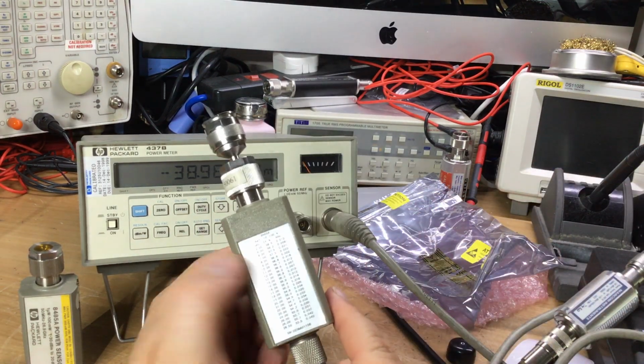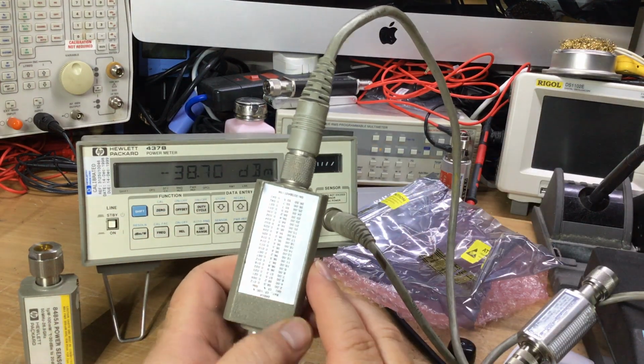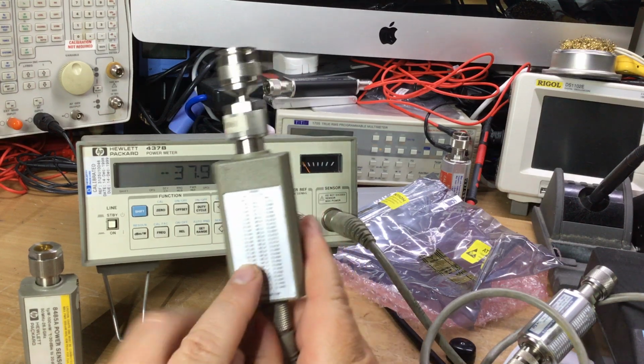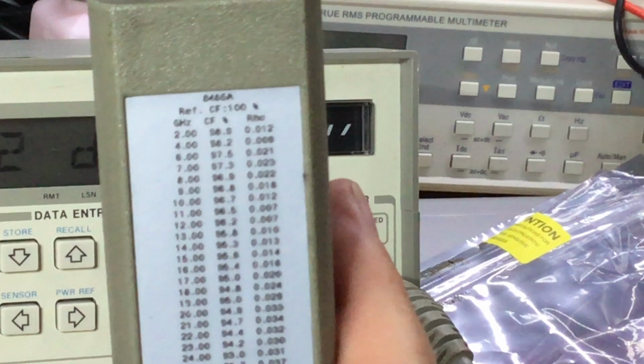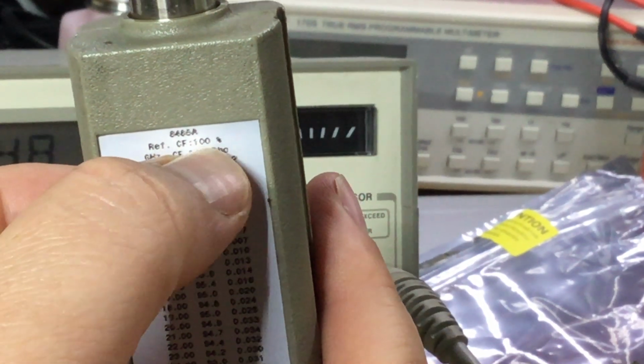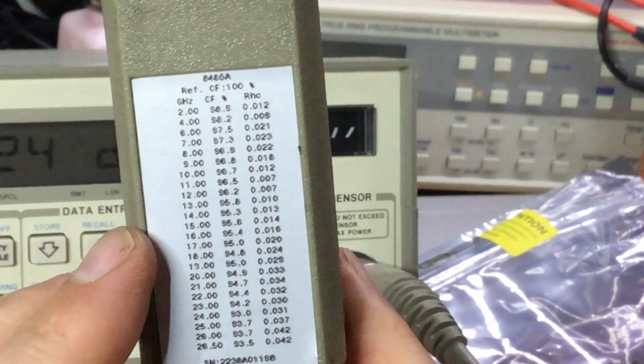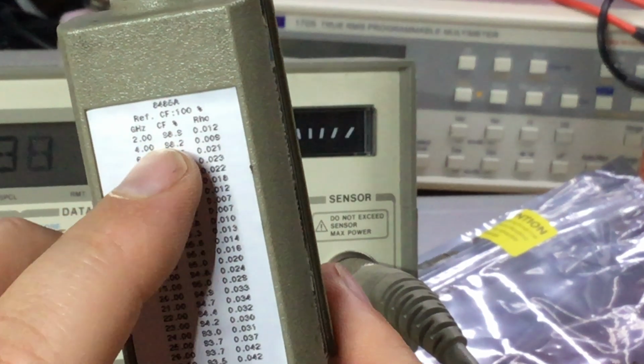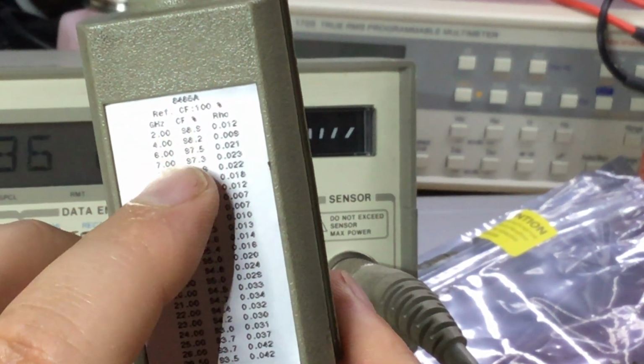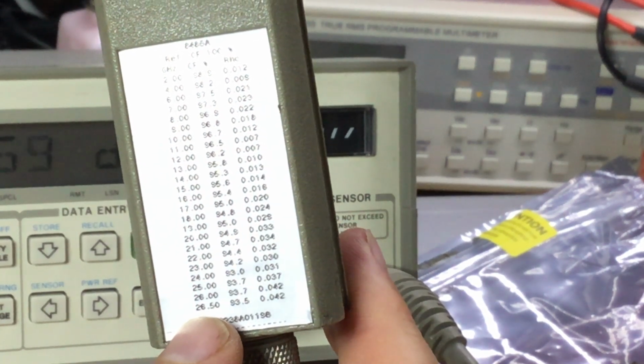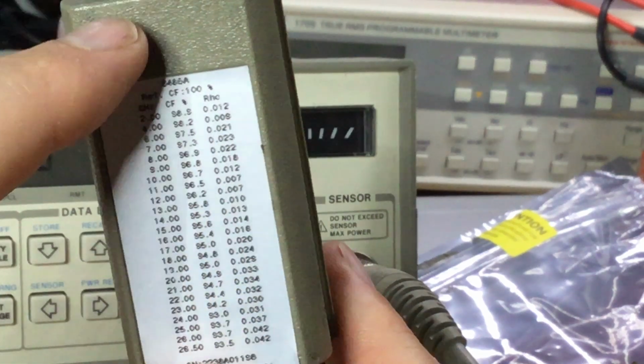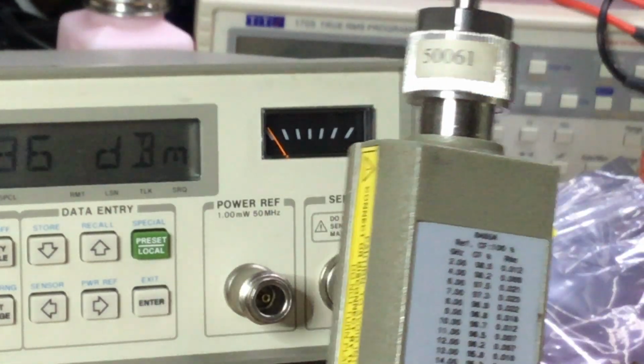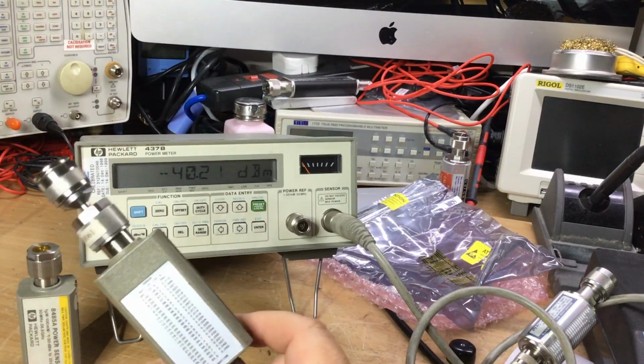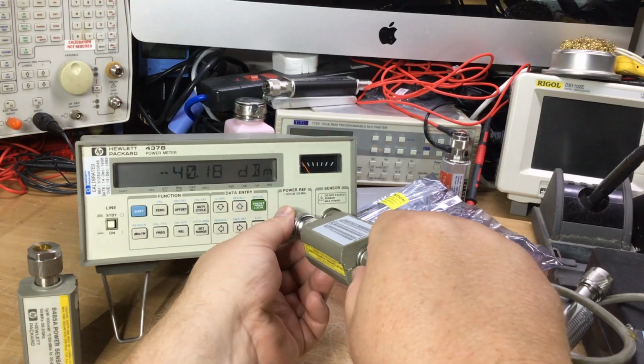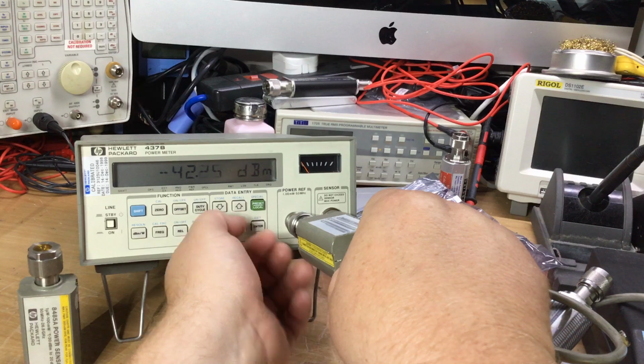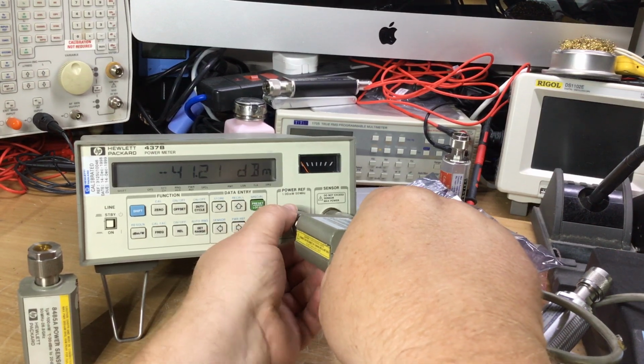Now the cal factor on this particular one, according to the table, is 100%. So basically this data, I've already entered it in, and we can see there, look, the cal factor is 100%. And then in the meter, which I've already done, you can enter the cal factor for each of the different frequencies, all the way down to 26.5 gigahertz. So after 1,000 years of entering all that in manually into the meter, then you actually get to a stage where you're ready to connect it and calibrate it. So that's essentially where we're at now. That's the only lengthy process if you want highly accurate measurements, obviously.